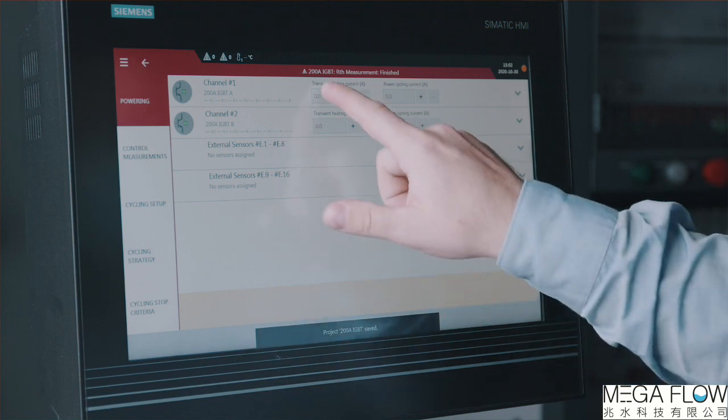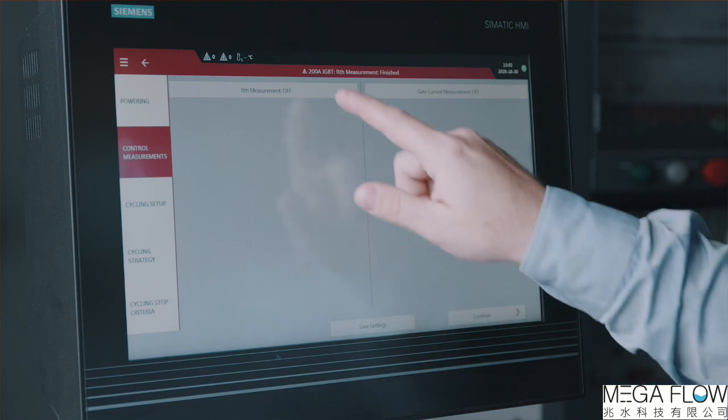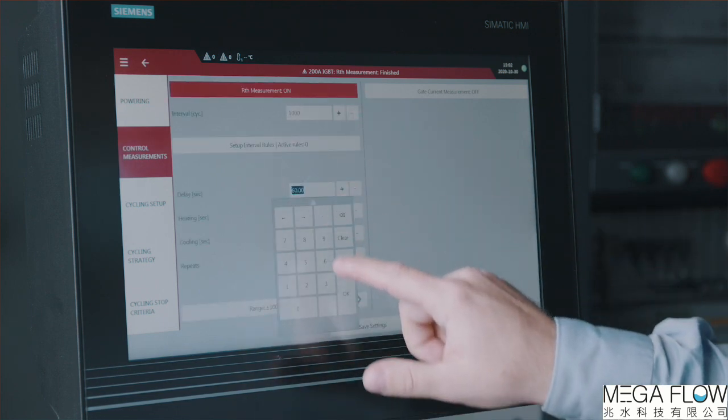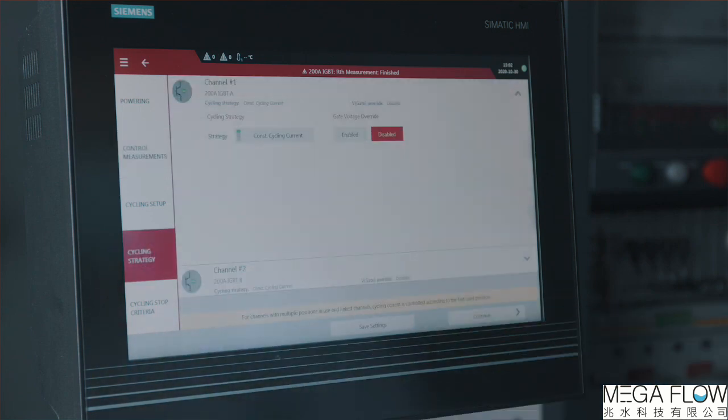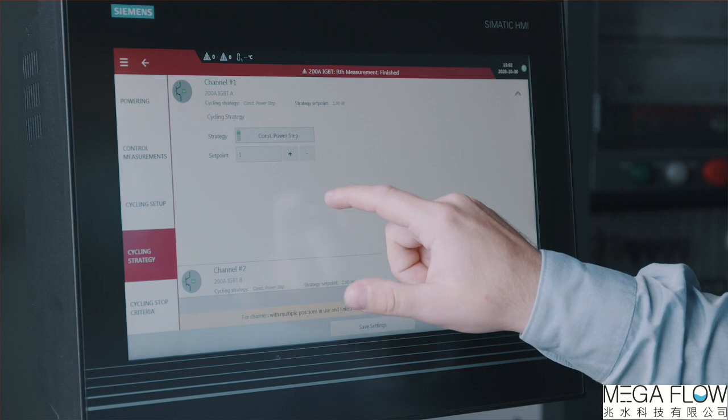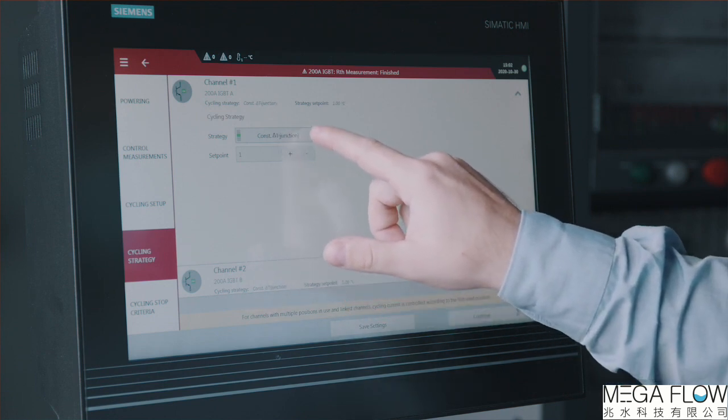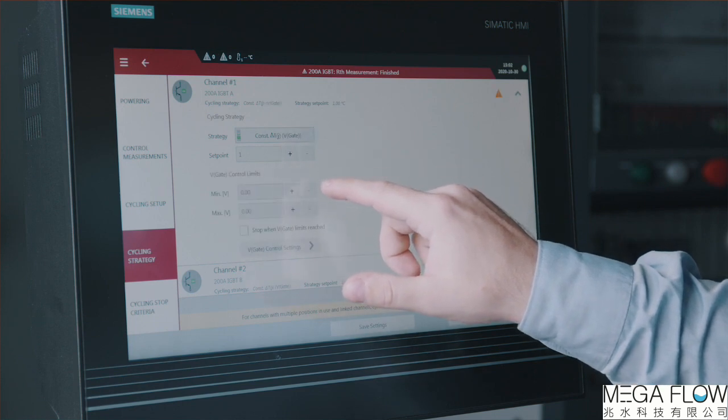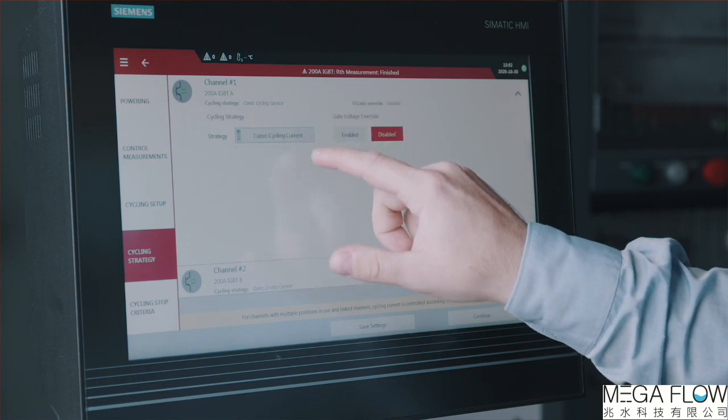Basic test parameters like heating current and timing parameters need to be defined. We can configure the automated thermal transient tests and optionally gate current measurement feature as well. There are various cycling control strategies defined in the control software. I can select how the system shall regulate the powering parameters with the device degradation. Current testing guidelines prescribe using fixed heating current independent of the device degradation to best mimic the real usage of the components. But there are optional methods to ensure constant junction temperature change or constant power step by regulating the heating current or gate voltage as well.